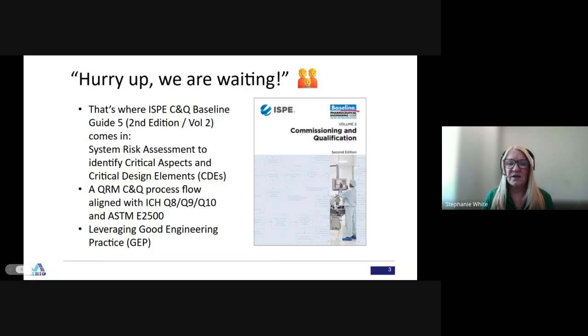So all these documents kind of flow together to create this process that we can use in our commissioning and qualification practices to reduce the level of testing. It's based off critical aspects and critical design elements that we test in qualification, and every other aspect or business need is tested in commissioning, and we can leverage that and even vendor testing for our qualification.